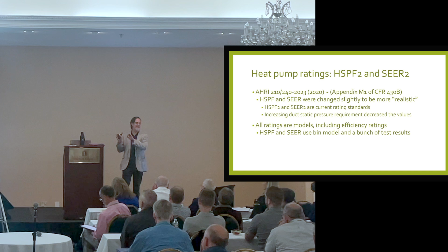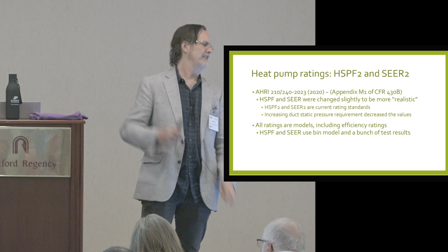Okay, I don't have a graphic, but you can all picture that. So basically, you take all the test data, and you say, how do I map that test data to the performance at different outdoor temperatures? And you multiply the performance at each temperature times the capacity delivered and the energy input for each bin, and you get the total capacity for the year delivered and the total energy input for the year consumed, and the ratio of those is your HSPF. Same as what I showed you earlier with the COP. It's just in BTUs per watt instead of BTUs per BTU.